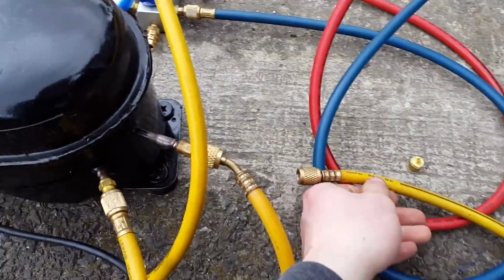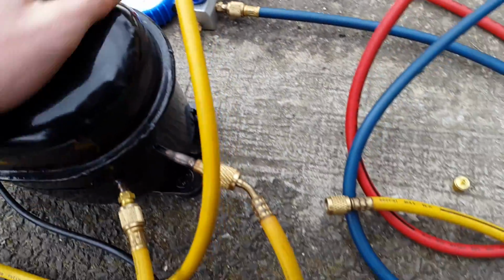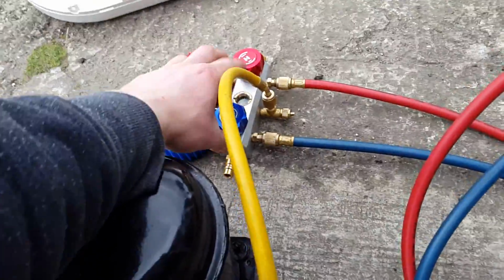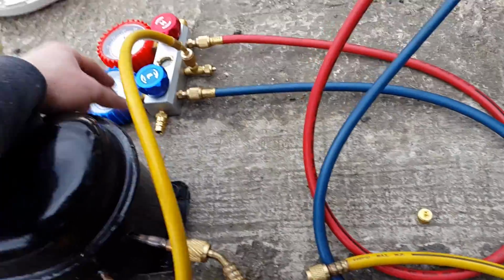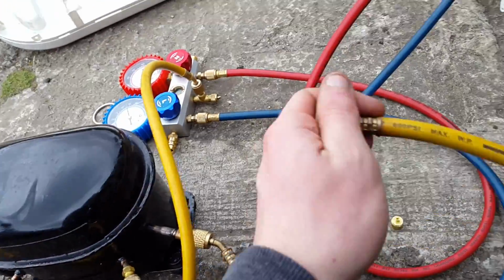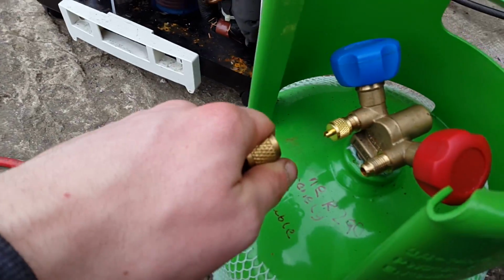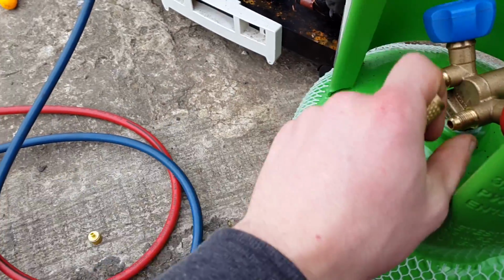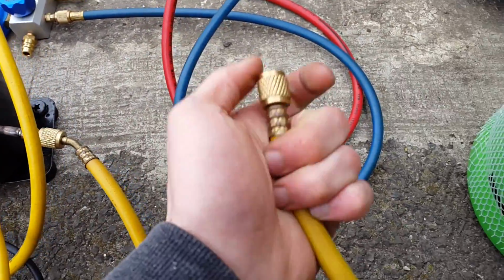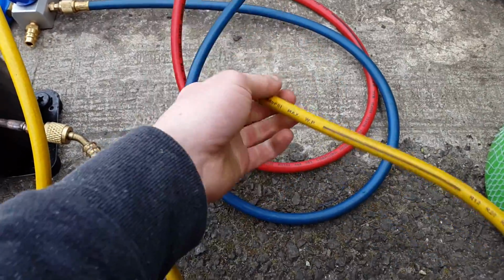Once the air stops flowing, I'll purge it through with refrigerant, just a little bit, until I'm sure there's absolutely no air left, then connect up to the cylinder and do a very small purge, just to make sure there's no air in it.